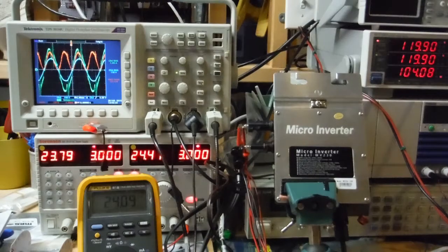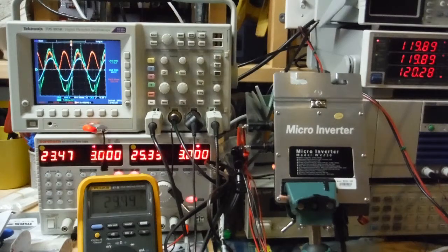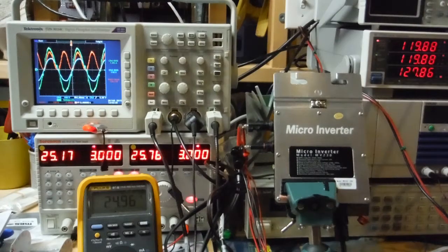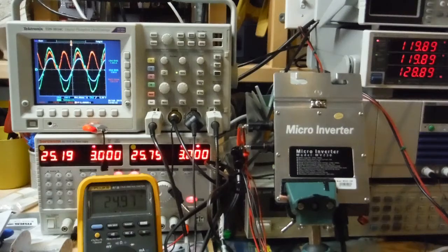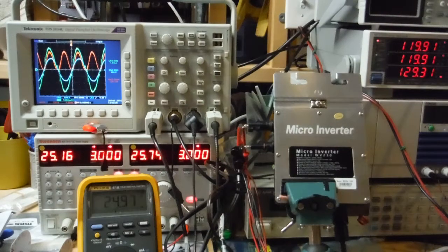I'm at 3 amps on both supplies now. And the power over here on this meter should climb back up close to 130. So the anti-islanding protection seems to work.